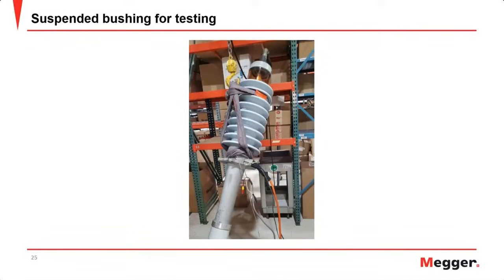I do see that there are some transportation requirements for OIP, but I believe it would be good practice to ensure that the bushings are at a particular angle. I can't say I know the exact number, but it should be close to vertical rather than lying down. Also important to note that they should be removed from any wooden crates they may be stored in. Those wooden crates, if the bushing is hanging or sitting on the ground flange, may create some external paths to ground, which we want to avoid.